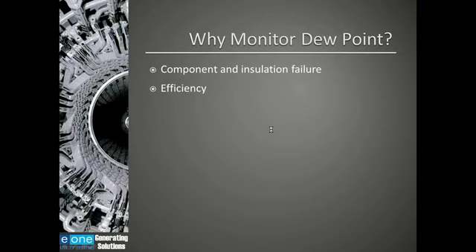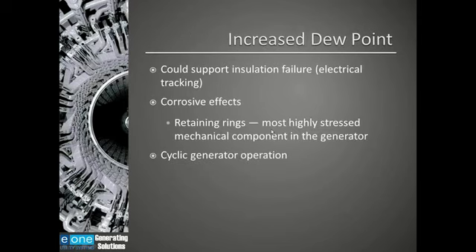Let me back up. Increased dew point can support insulation failure, electrical tracking. Usually this takes place in the rotor, on the rotor windings. Also, a higher dew point has a corrosive effect on some generator components. The retaining rings, which are the most highly stressed mechanical component in the generator, it's very important that you maintain the integrity of the metals, the retaining rings. And there are certain metals that become affected by having a higher dew point in the generator to a point where they can break down.